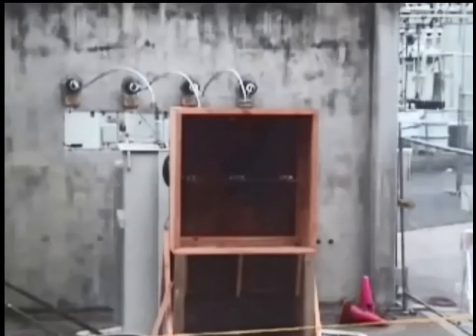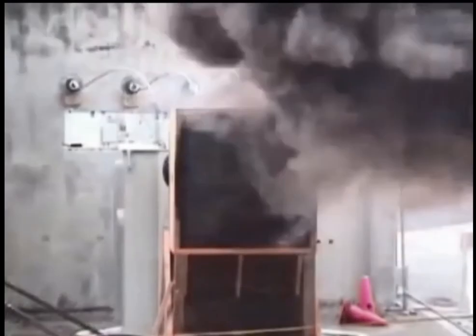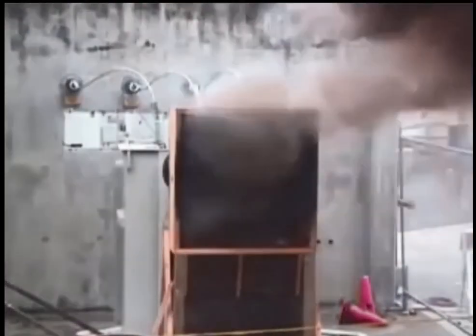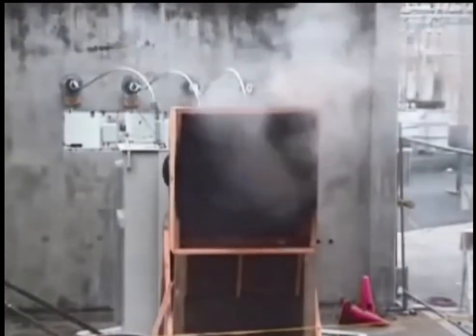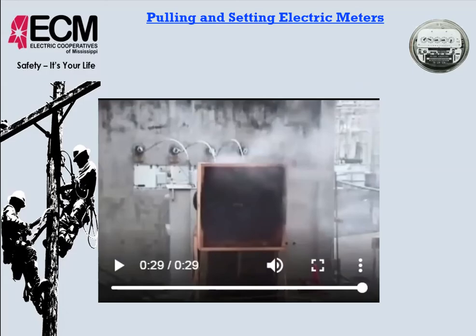480 is a voltage that we should not work energized. 480 will self-sustain until it actually burns itself clear. See how violent it is, how hot, how far it comes out. If you have 480 in a self-contained meter base with very large wire, that's going to be very devastating to you. The next video we're going to look at is relatively short, 29 seconds, maybe just a little longer.